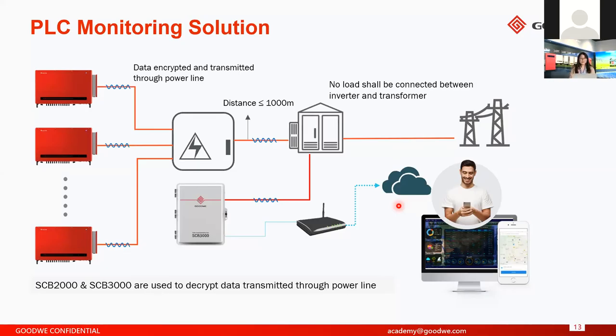Currently, the example I'm showing is with the GoodWe HT series. For the HT series, we have to use SCB3000, but for the GoodWe MT series, you can use the SCB2000 series. SCB3000 is an upgrade from the previous SCB2000, and the communication is more stable and it can connect and support more devices, I mean, more inverters. The maximum distance between the inverters and the transformer is one kilometer. But as I said previously, no load shall be connected between the inverter and the transformer, because that would interrupt the data transmission between the inverters and the SCB3000 or 2000.